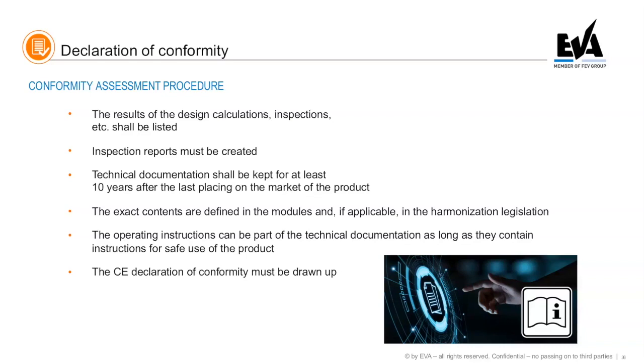So everything should be easy going. The operation instruction is quite important, not only to have a safe use, but it has to be part of the technical documentation. It can be part of the technical documentation, but it has to be provided. So technical documentation is nothing without the operation instruction. This means the operation instruction has to contain everything for a safe use of your product.